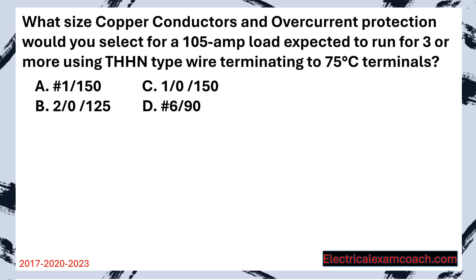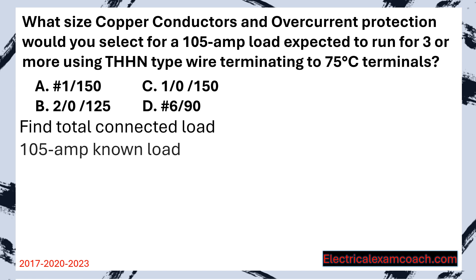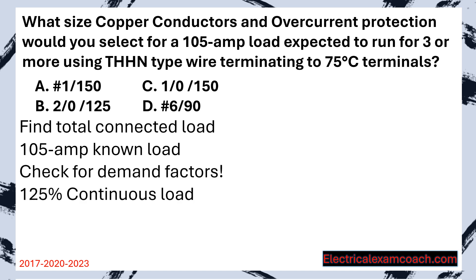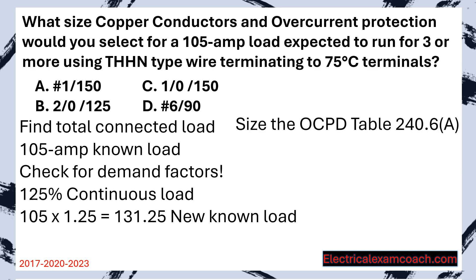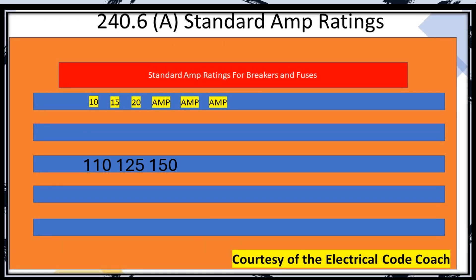What size copper conductors and overcurrent protection would you select for a 105 amp load expected to run for three or more hours using THHN type wire terminating to 75 degrees C terminals? Step one: find the total connected load — 105 amps is our starting known load, but we must check for demand factors. We find that we have the 125% continuous load rule, so we do our math: take the original starting known load and multiply it by 1.25, giving us a new known load of 131 amps. Now we size our overcurrent protective device — we head to table 240.6A and choose the next standard size, which is a 150.